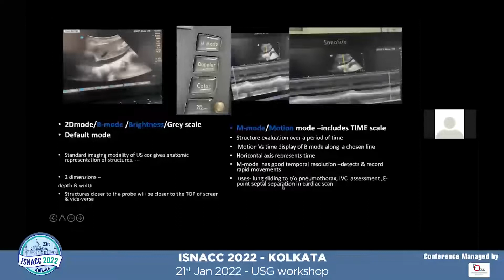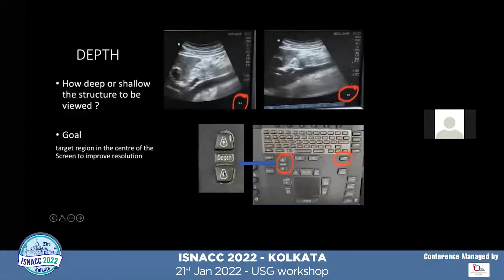So now comes the depth. It is the first setting that needs to be adjusted when you start scanning, and it tells us how deep we want to scan. And you can see here, on the right side of the screen, there is a scale of depth in centimeters, and at the bottom, the exact value of the depth is displayed. So our goal is to keep the area of interest in the center of the screen to improve the quality of the image. There are 2 keys on the control panel. The upper one decreases the depth, and the lower one increases the depth.